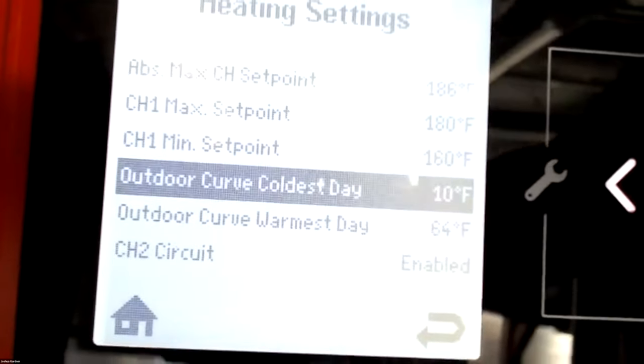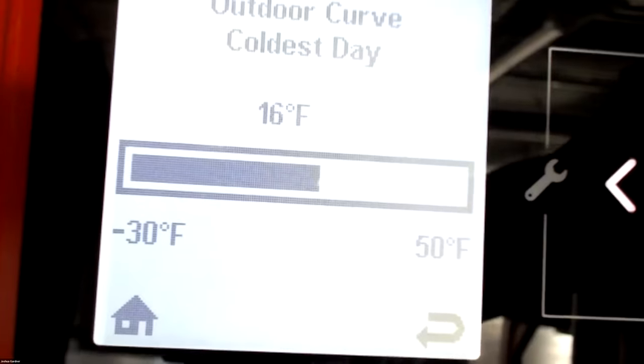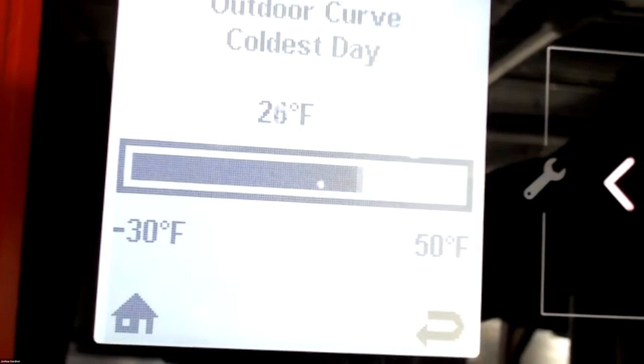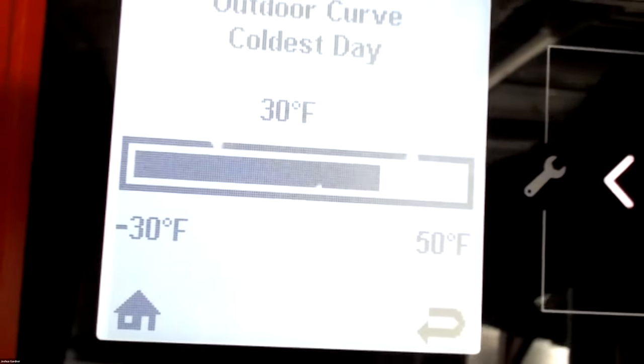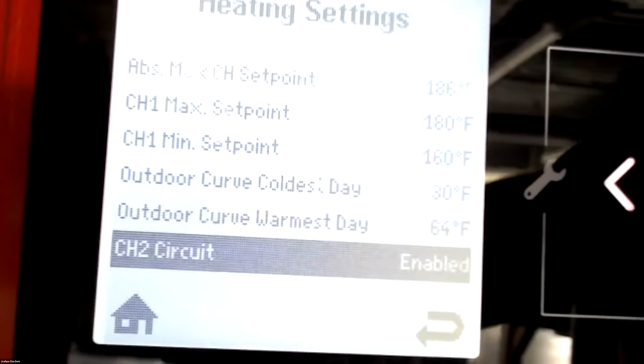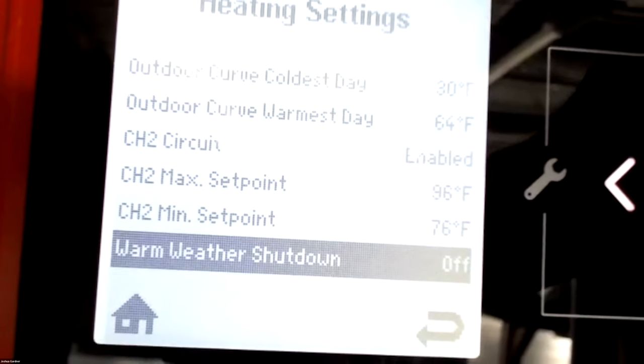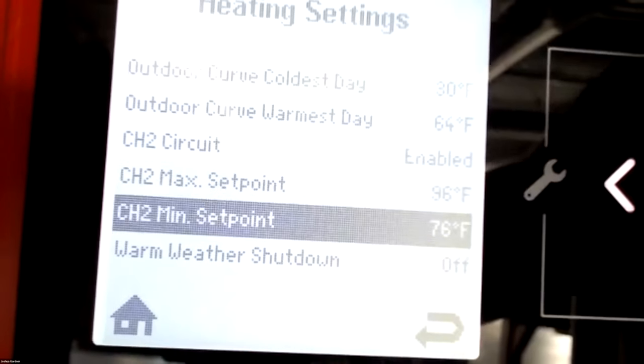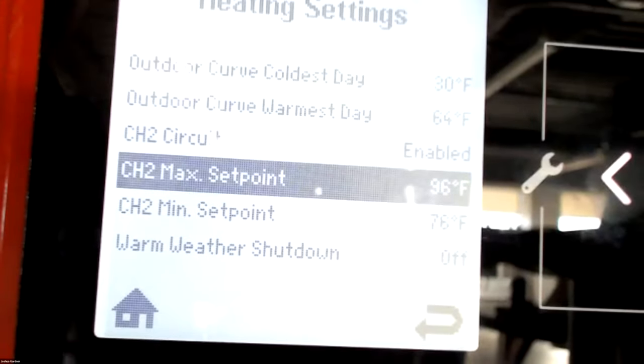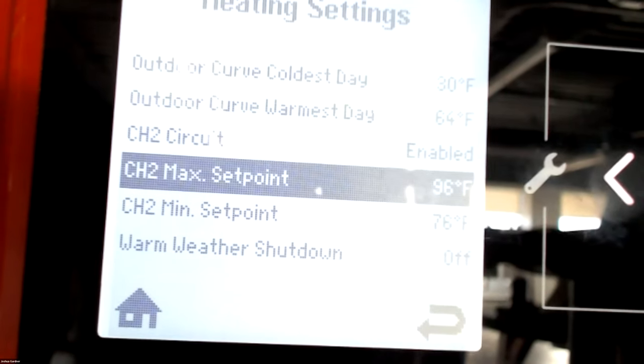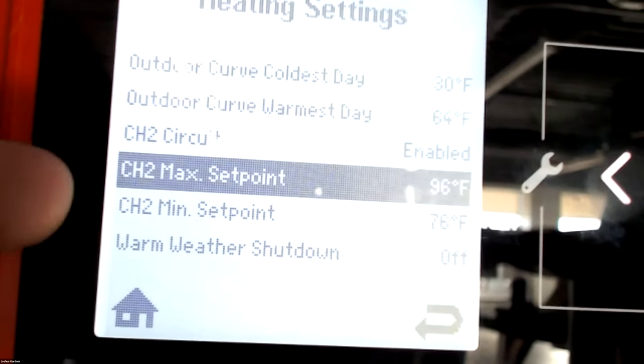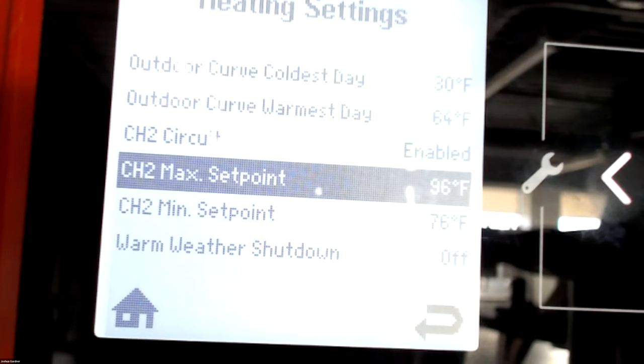And then my coldest outdoor curve day, I'm gonna bring that up 30 degrees. So that's where we can adjust that there. And then if we go down, we have the CH2 settings for those temperatures. It still utilizes the same outdoor and warm weather designs that we put up in CH1, but this, we just change our max set point and minimum set point.